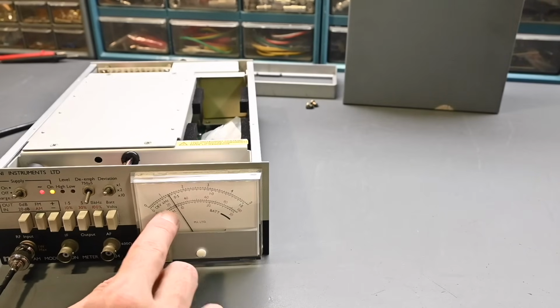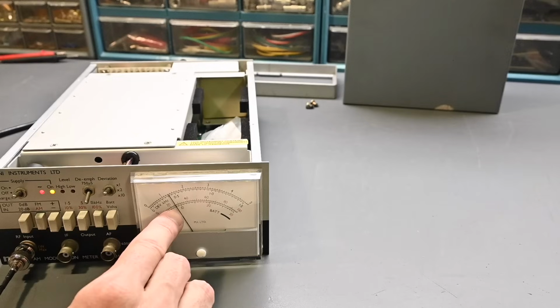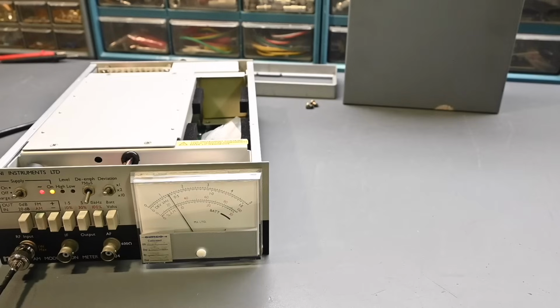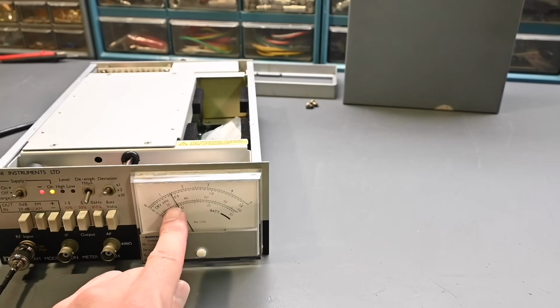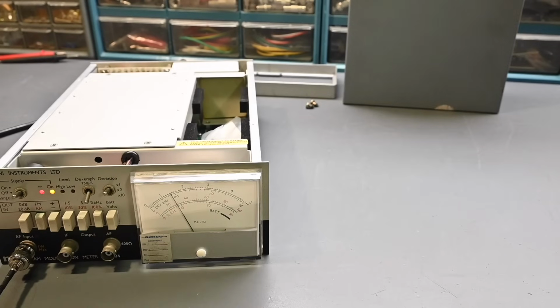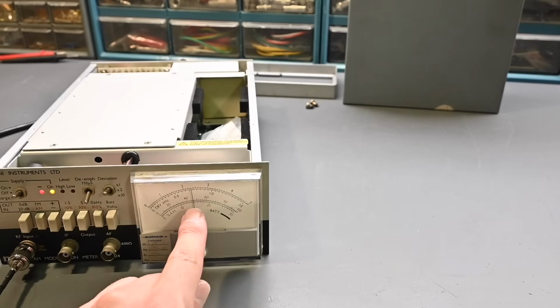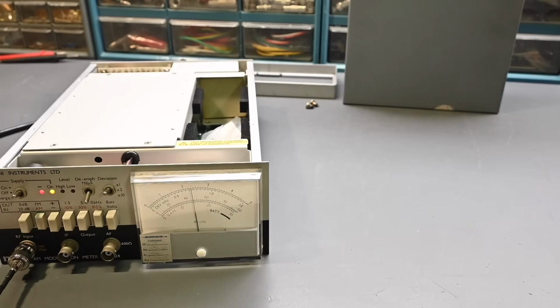yes, it's right. See, again, it's just a little bit under. It's very close to the tick mark for 30. So if I go 30, 132, it's the same thing. See, now I went 2% higher and it's right on. So there may be something else in the meter that's just off ever so slight, but it's only 2%. It's very close. So if I wind this all the way up, let's go to 50%. See, 50%. It's reading just a little bit under consistently on the AM, so perhaps there's something else.